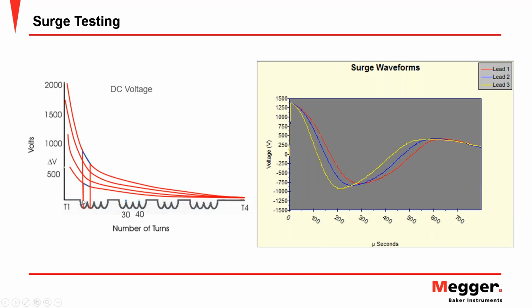And as the surge voltage and the current flow that results from that release of the capacitor penetrates the winding, there's a non-linear voltage characteristic that's developed across that coil. And this establishes some voltage difference between adjacent turns within the first coils, so that we can evaluate that copper to copper or turn to turn insulation. And if there's any insulation weakness there, we'll look at that in the form of variation in the surge waveforms that result for each of these phases. So that's kind of what we're doing there with the surge test, again, to evaluate a different part of the insulation system that low voltage testing would just miss altogether.